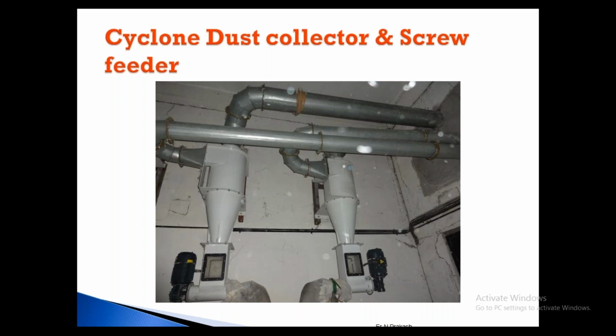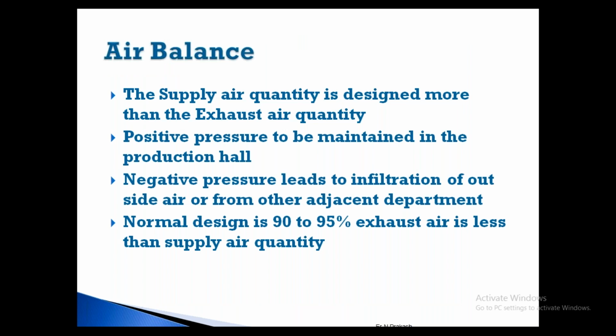There you have a screw feeder, and motorized screw feeders are there. Earlier they used to have collection bags, so manually they used to collect with a bag. Nowadays we have a screw feeder, so the volume of waste will be compressed and comes out in compressed form. Continuous waste will be collected here, as well as continuous collection of dust from the rotary filter. Because the waste is continuously collected in the rotary filter, the air collected from the department is getting cleaned totally. All the waste is collected through the return air systems. So it is continuous working, so that you will be able to maintain the required conditions in a dust-free situation in the production hall.